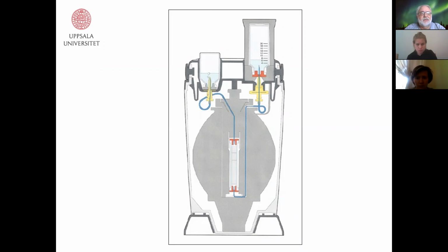One standard 34 gigabecquerel generator of technetium costs the same money as indium for 2 patient doses. And with such generators, you can run tens and probably hundreds of patients. So this is the biggest advantage.